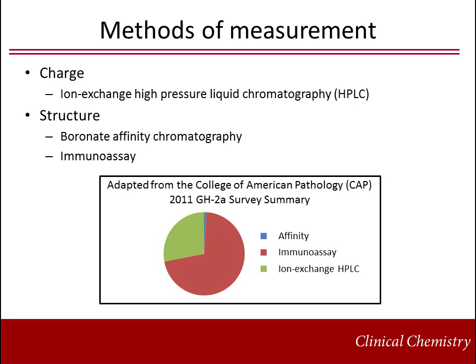Based on recent College of American Pathologists survey data, approximately 29 hemoglobin A1C methods from 10 manufacturers are currently in use in clinical laboratories. Most methods can be classified into one of two groups according to assay principle. The first group uses methods that measure hemoglobin A1C on the basis of charge differences between glycated and non-glycated components, which includes cation exchange chromatography. The second group uses methods that separate components on the basis of structural differences, such as boronate affinity chromatography and immunoassay. Most charge-based and immunoassay methods quantify hemoglobin A1C defined as hemoglobin A with glucose attached to the N-terminal valine of one or both hemoglobin A chains. Boronate affinity methods detect not only hemoglobin A1C, but also other amino group glucose adducts, such as glucose lysine adducts and glucose chain N-terminal valine adducts.